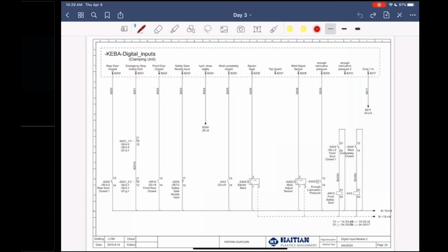Now, to reiterate, you have your rear door closed and your front door closed and your e-stop. As I mentioned yesterday with the Pilz, you have 2 signals on the Pilz that also have the rear door closed, the e-stop, and the front door closed. Each door has 3 limit switches on them. So one limit switch will control this. The other 2 limit switches will go to the Pilz to make sure that the safeties are active. Same with the e-stop and same with the front door.